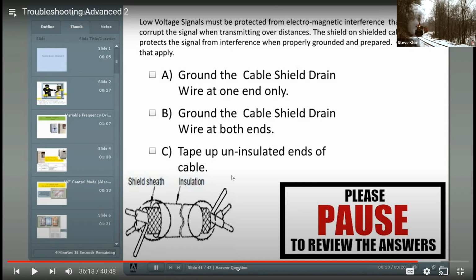In other words, you cut the jacket back on the outside of the cable because you had to get the other two wires out. Then you trim back that shield wire as far as you could, but there's a little bit left and it's kind of fuzzy on the ends. That's where you want to get the tape on, between the outer case of the cable and maybe a quarter inch past where those frayed ends are.